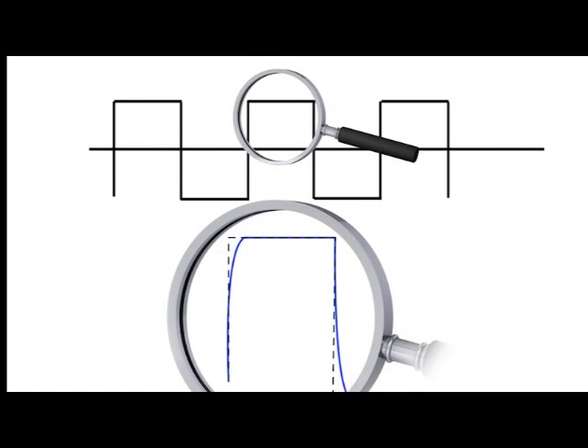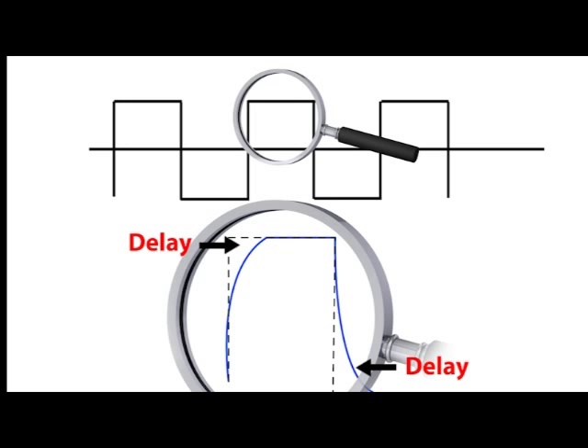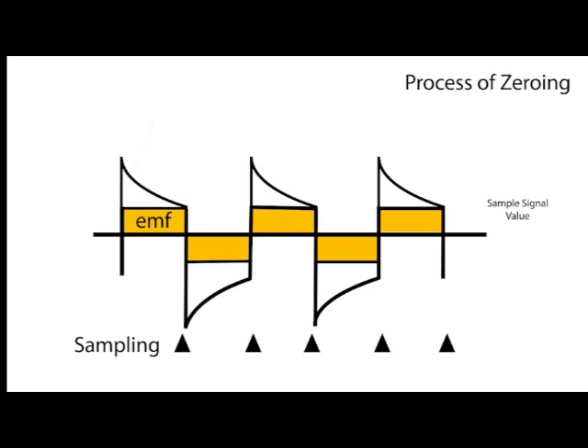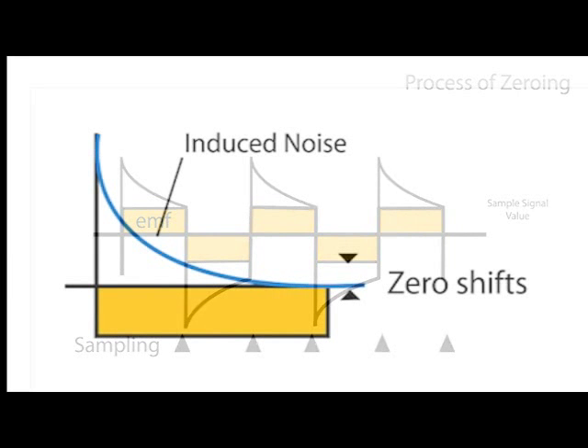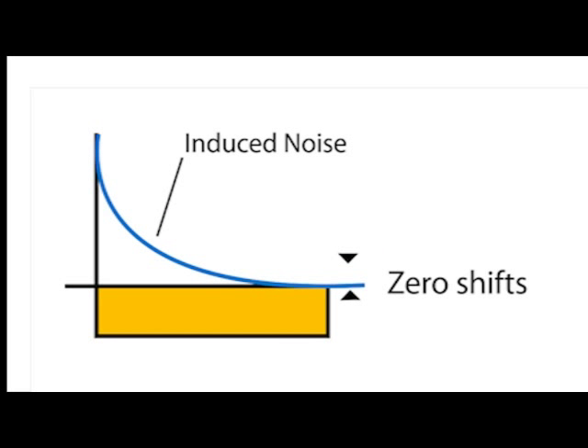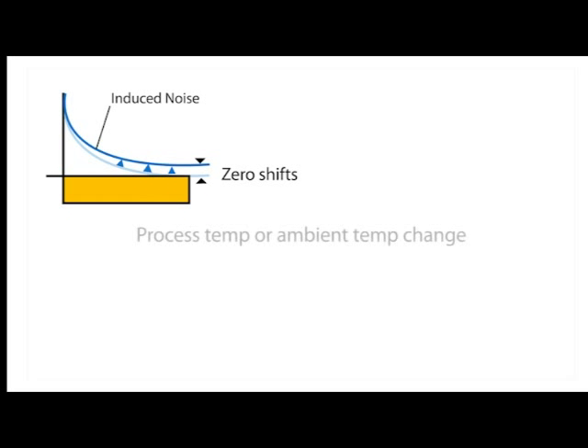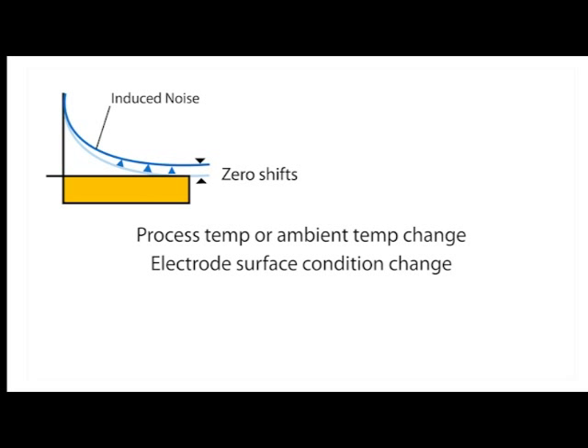These induced magnetic fields delay changing of the magnetic field generated by the coil drive. Although zeroing off any changes could initially bring the signal back to a repeatable value, the shape of the signal waveform of induced noise may change with time. This could be caused by a variety of influences, such as process or ambient temperature change, electrode surface condition change, or adhesion in a flow tube.